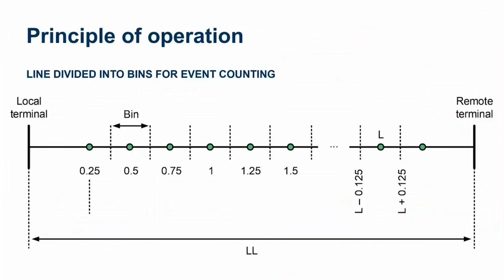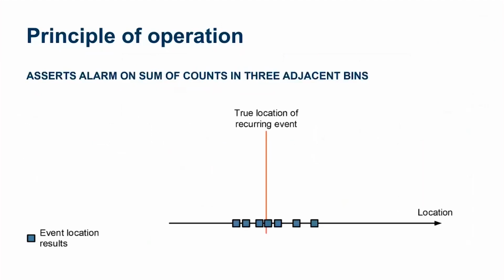So again, our line is divided into quarter mile or quarter kilometer bins, and we're going to be tracking the precursors that we're seeing at each quarter mile section. So we can see here we've got some bins. This is the true location of the fault. And then the event location is shown here in these blue squares.